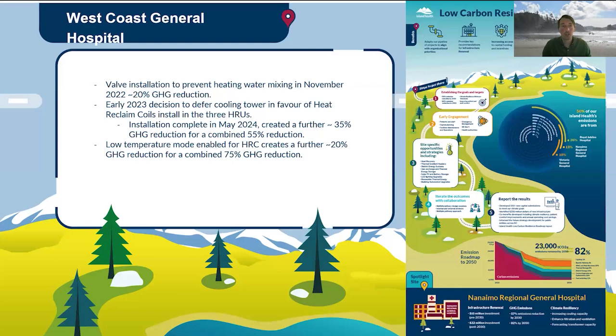And then just this last January, we've been working with our on-site technicians and our equipment supplier being trained for these multi-stack units around the operational set points. And so we had realized that there was a low temperature mode that we could enable for the heat recovery chillers that would allow us to operate at a lower set point. And when they were installed and commissioned, they were just put into standard mode. And so we had to go through a bit of a process there to verify that we had the right glycol mix for the system to be able to utilize this. But as soon as we had enabled that, we got a further 20% emission reduction to combine to almost what our 2050 goal is within BC of an 80% emission reduction.